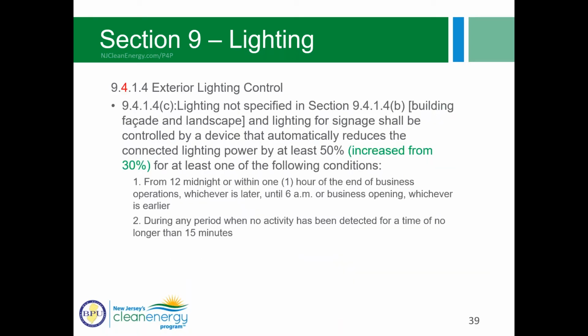Exterior lighting control. So 9.4.1.4, again, is one of the mandatory ones. This is about turning lights off automatically when sufficient daylight is available. They updated that lighting not in section B, which is the building facade and landscape, and lighting for signage, must be reduced by 50%, which is increased from 30% back in 2010. So they've upped the amount that it has to be reduced. Also, this is a mandatory control, and it applies if it meets one of the following conditions: from 12 midnight, within 1 hour, or during any period when no activity has been detected.